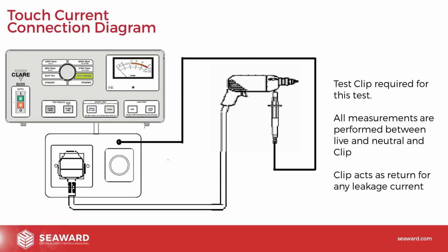So again, much like before, here's a typical touch current connection diagram. Now, we've shown the B255 because there is an important point to note with regards to test clip placement when performing the test. In order to perform the touch current test, we need to provide a return back into the instrument. For those of you that have a SafeCheck 8, the return path is simply the black crocodile clip that's supplied on the device. That's plugged into the back of the unit, and everything's fine.